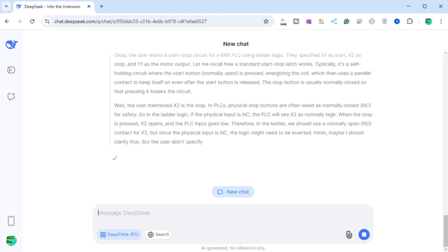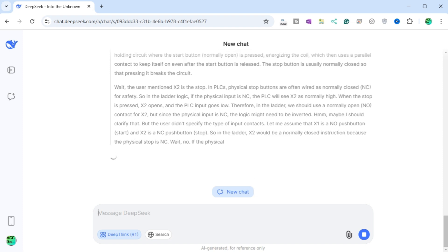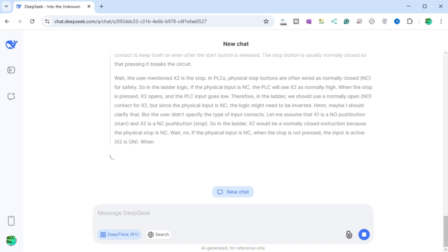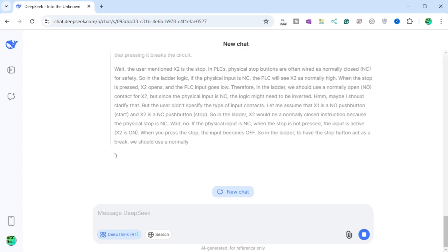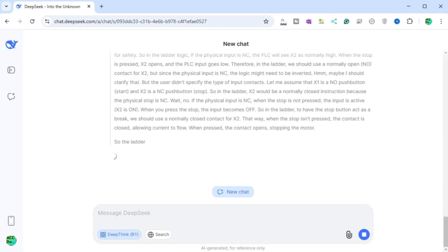DeepSeek works out the ladder structure: assuming X1 is a NO pushbutton (start) and X2 is an NC pushbutton (stop), in the ladder X2 would be a normally closed instruction. The correct start-stop structure has the stop NC contact in series with the combination of start X1 NO in parallel with the motor latching contact Y1 NO, then the Y1 coil. So when X2 is closed (stop not pressed), pressing X1 energizes Y1, and Y1 latches through its own parallel contact. Pressing X2 opens the contact and breaks the circuit.